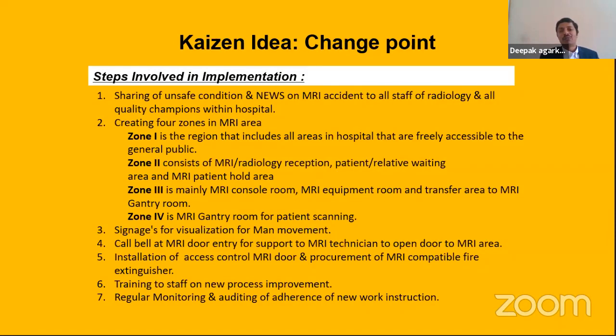These zones are very, very important as per the ACR standards. Zone 1 is a region that includes all the areas in the hospital that are freely accessible to the public. Zone 2 is when the patient enters the MRI or radiology reception. Zone 3 is basically where the MRI console and MRI magnet equipment room is and transfer is happening. Zone 4 is where the MRI gantry room is, where the magnet is.